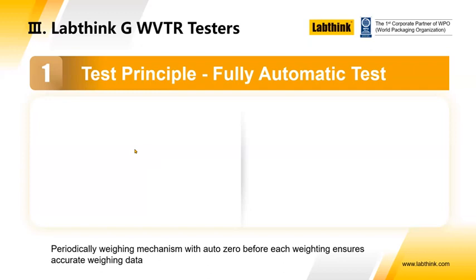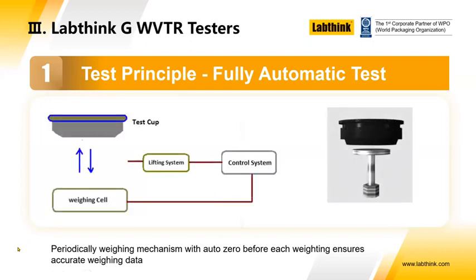Anyway, let's look at the test principle for the fully automatic test. So we have a test cup, the weighing system, the lifting system, the control system, all parts of the automatic system. And the control system controls the handling of the cups and the measurements, so that it periodically weighs each of the cups, auto zeros before each weighing, and ensures accurate data by doing so. So it takes away the scope for manual errors.